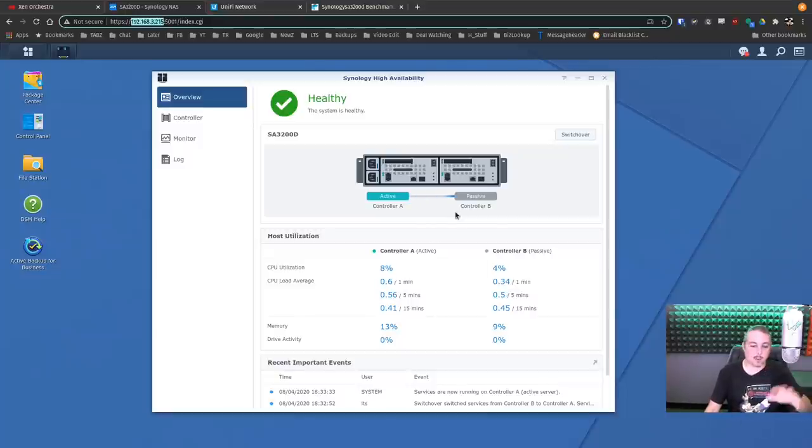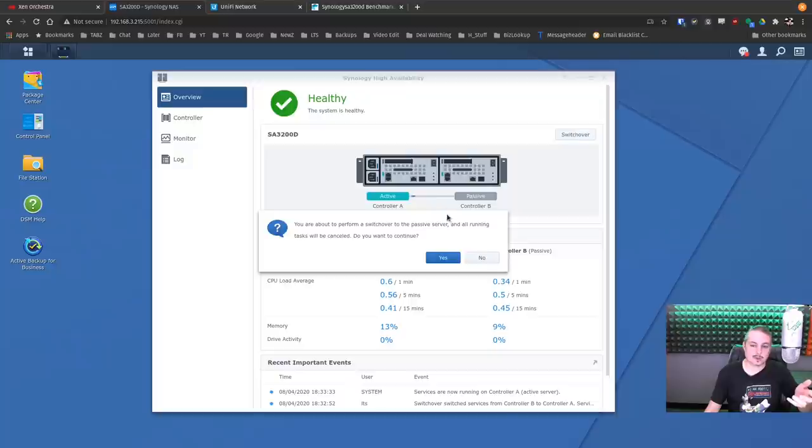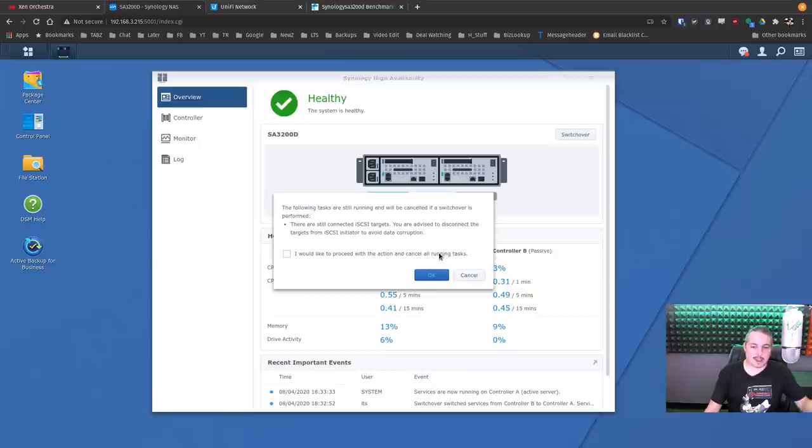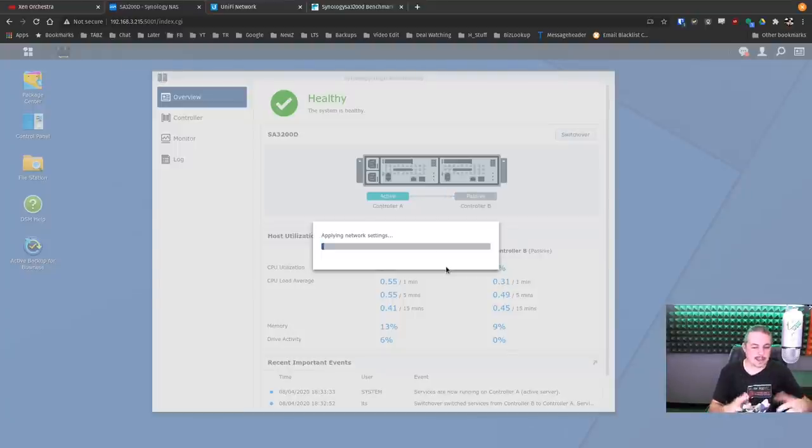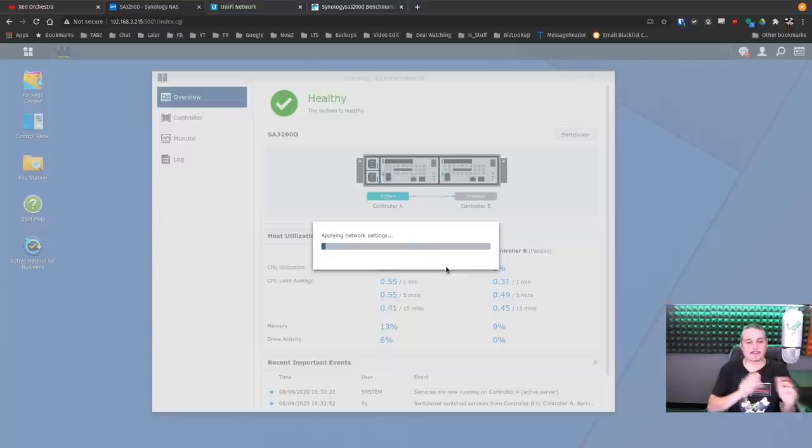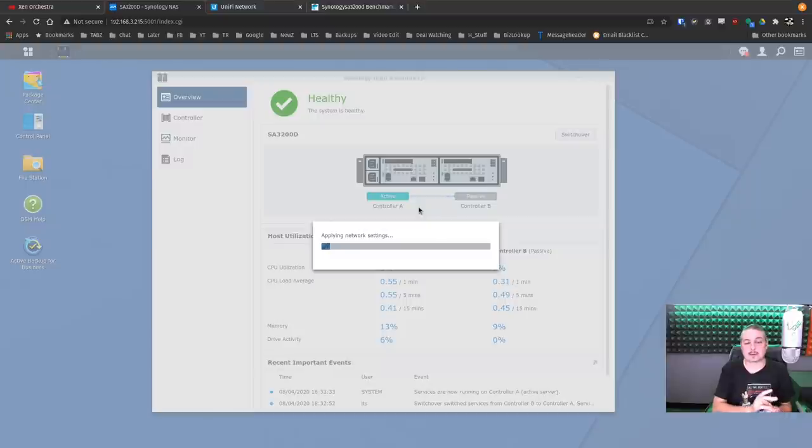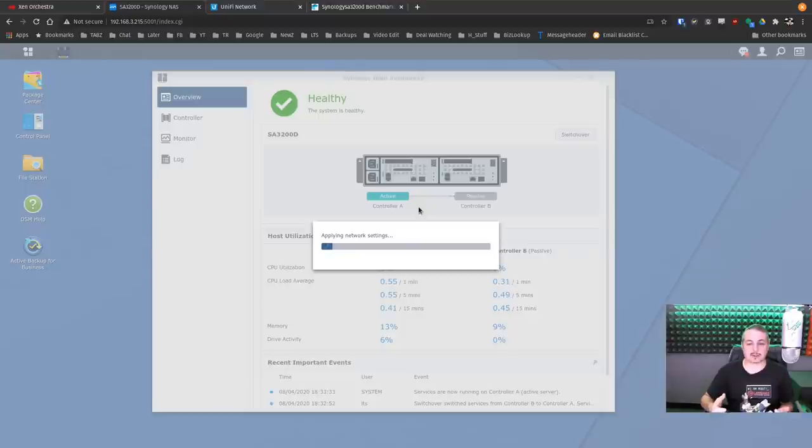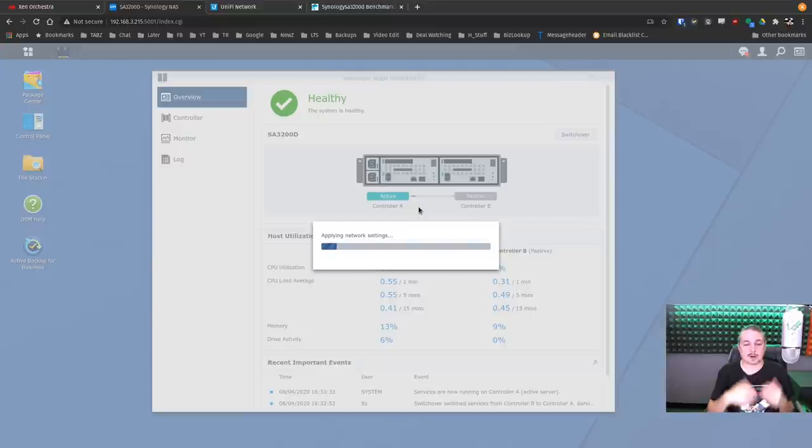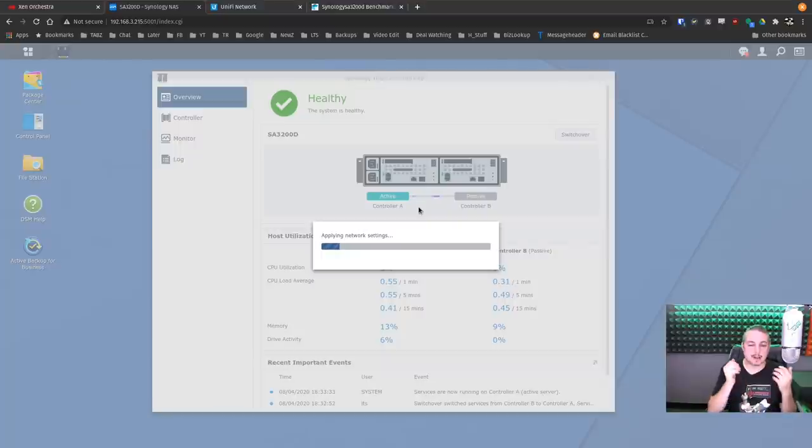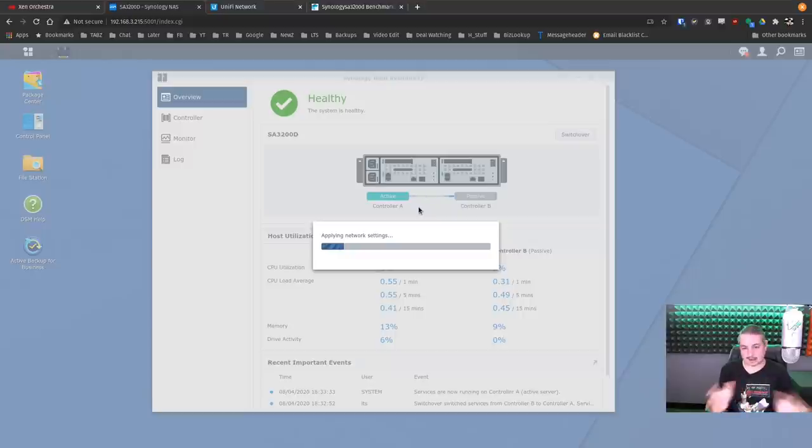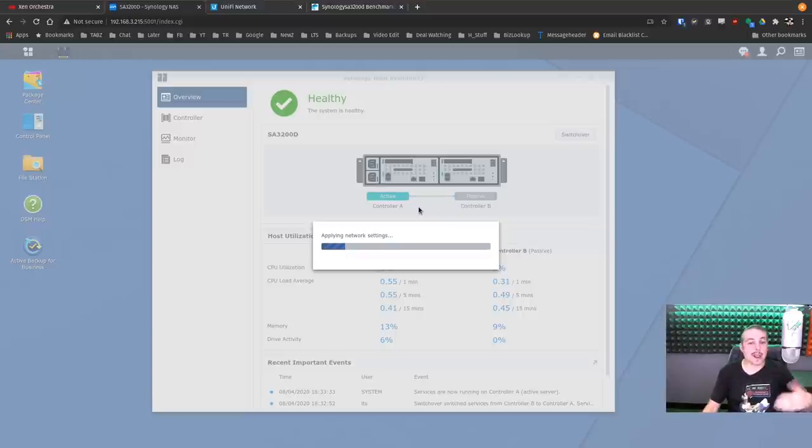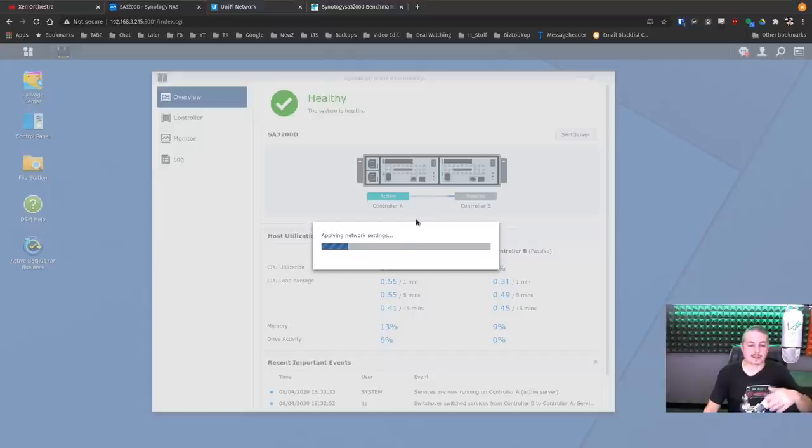When we switch these controllers, it's not flipping the MAC addresses, only flipping the IP address assignments. There's a couple ways this can happen. One, we can do switchover, and we'll do that real quick here. The two devices stay in sync with each other by a transparent backplane that is between the active and passive controller. They don't need any of the network interfaces to be plugged in for the two devices to talk to each other. That's how they stay in sync. Anytime you load a feature or set something up inside the active controller, the passive controller always immediately gets those settings, even if the network is not talking, because the backplanes talk to each other. They're both talking to the drives at the same time.